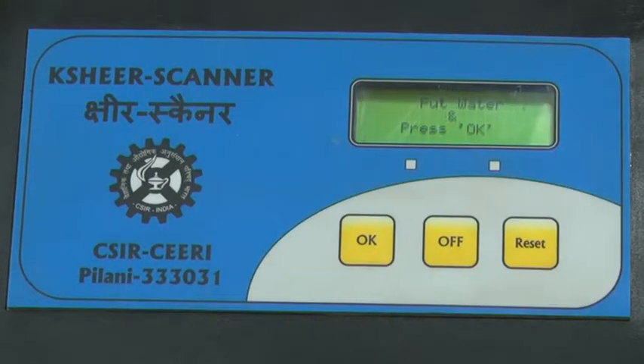The system is being aimed at being set up at milk collection centers in villages. Kshir Scanner is based on an electrochemical measurement technique wherein an array of electrodes developed at CSIR-CEERI is used for extracting the signal of interest.